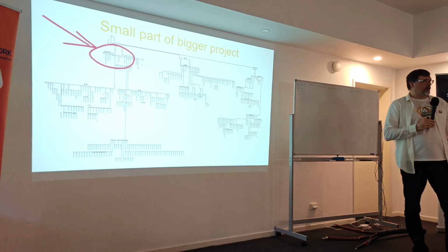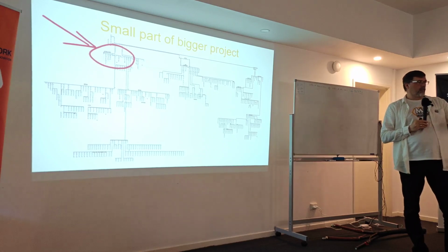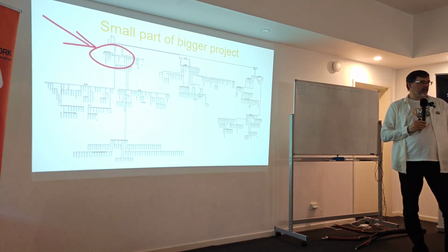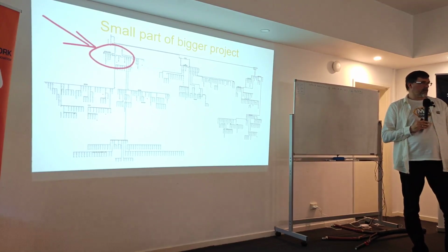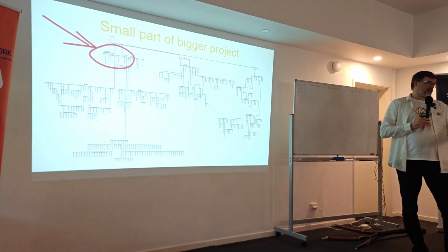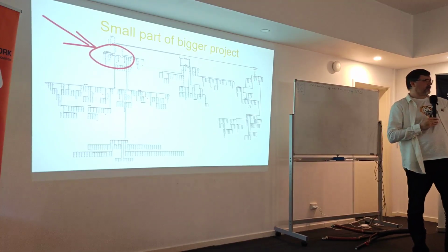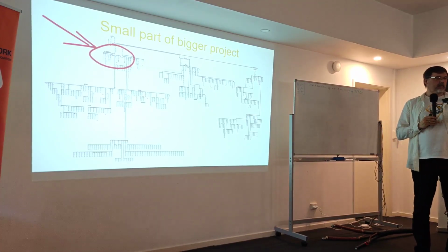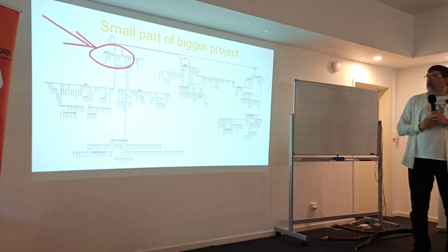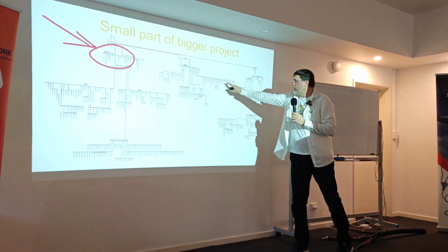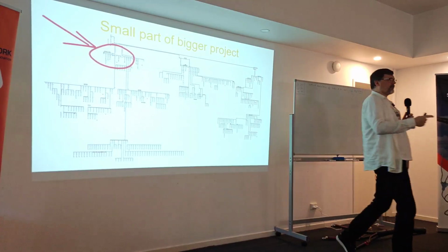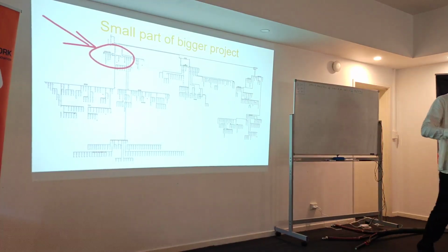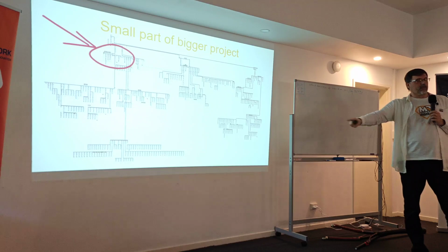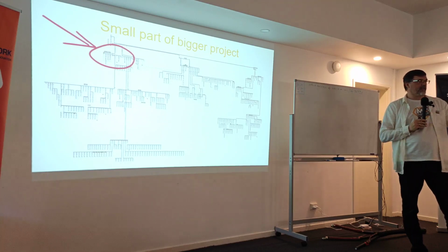So the checking, revisiting what they were saying, was good, because you go to site and you actually find out that we often have transformer 1, transformer 1, transformer 2, because people are ordering from different companies, and they will have transformer 1, transformer 2 on the drawings. And they have like 4 transformers 1, 2 transformers 2, some transformer 3. Everything is called low voltage switchgear 1, Q1, Q1, Q2, and I said, yeah, but we all have a problem, because in software like this, you cannot use Q1 as a name, because it has to be unique. So you have to be creative to make it LV1 Q1, LV2 Q1 or something, so it's easy to identify.